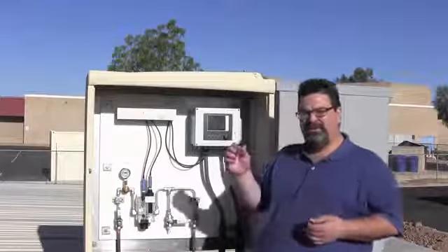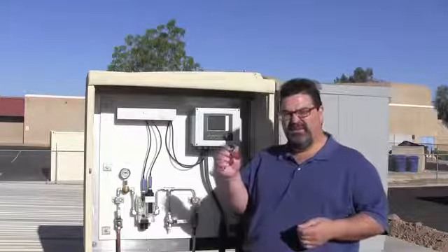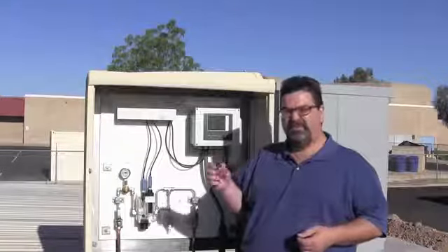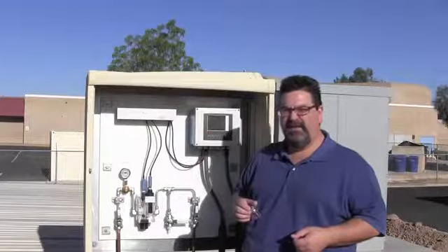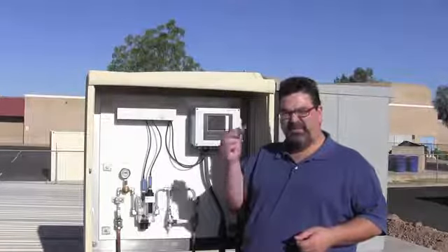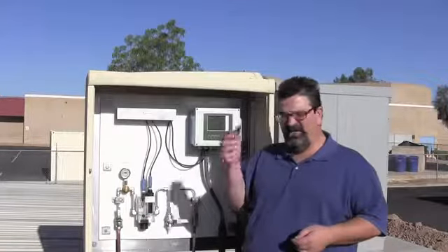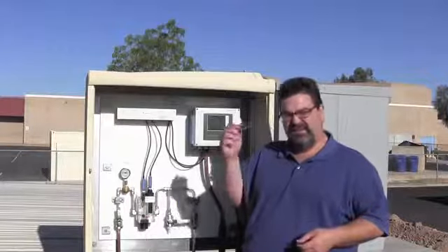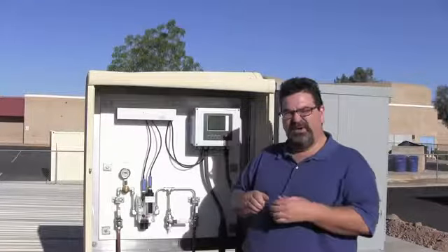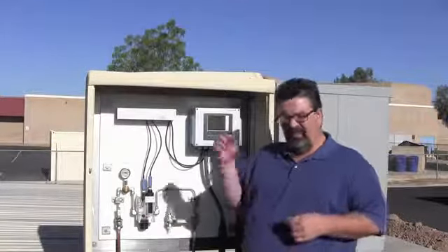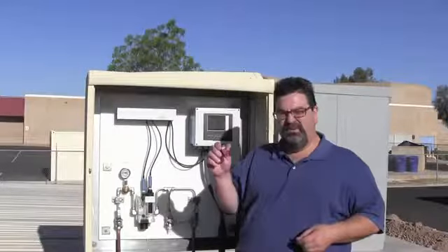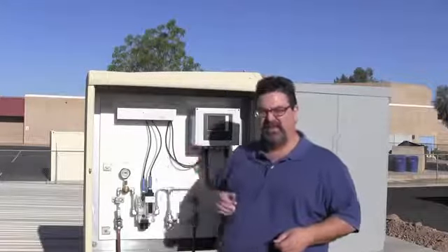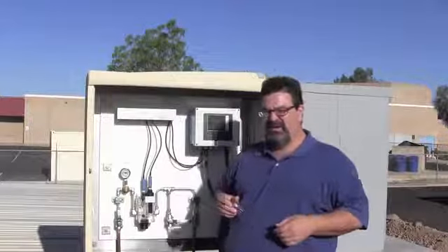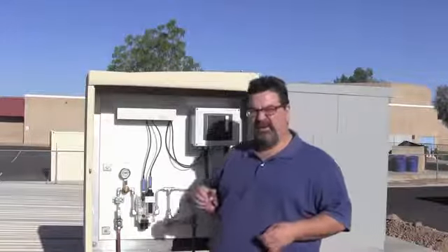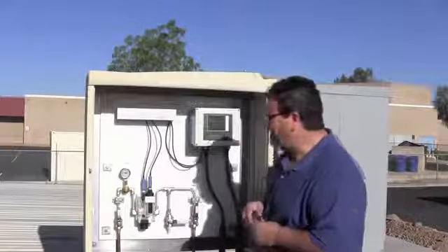First thing we want to tell you is when you take your DPD test for reference, please take multiple samples before you decide to calibrate the chlorine analyzer. There are many variables that can affect this reading, including the cleanliness of the glass, the time since you add your reagent before you take the reading, and the water level. So we want to take several readings to get an average before we make a calibration. Now let's hone in and look at the simple steps that are required to do a calibration.